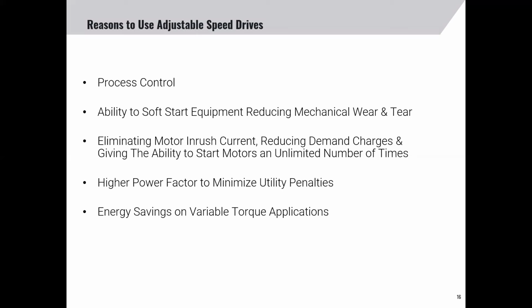And probably the most common reason to use an adjustable speed drive is the energy savings on variable torque applications. If you understand the affinity laws for centrifugal pumps and fans, you can eliminate mechanical dampers and valves in your system. So for example, if you're running a centrifugal pump and you wanted to reduce flow without a variable frequency drive, you would have to use a valve and reduce the flow. But with a variable frequency drive, all you have to do is reduce the frequency. And if you reduced it by 20%, you'd actually need only about 50% of the power to run the motor. So you'd have a significant savings. So those are just some of the reasons why you would use an adjustable speed drive.